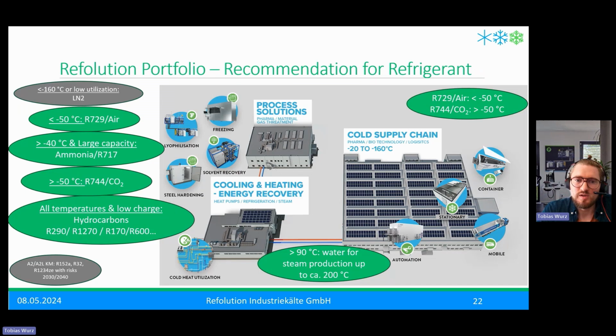In the next slide, I will show you where we use all these natural refrigerants, where for each application we say we can use natural refrigerants. For example, for ultra low applications, where we are very strong, like the cold chain supply, we have air as refrigerant for -50 and lower, and above we would use, for example, CO2. For all these process solutions, we have even more refrigerants to choose from.